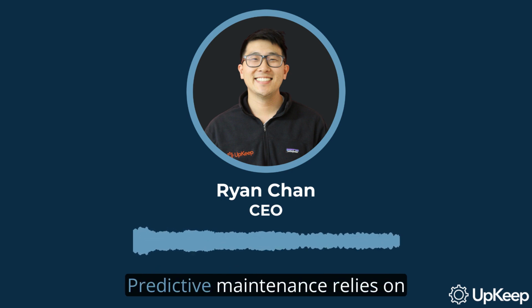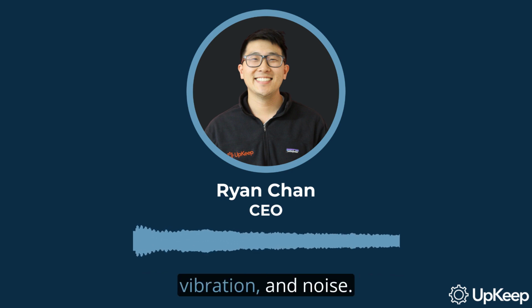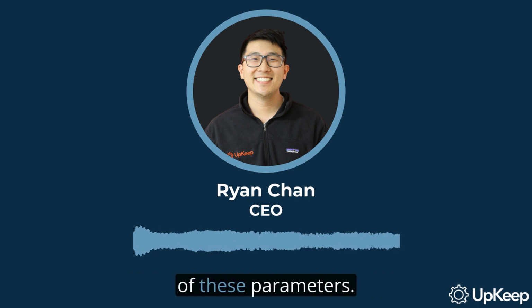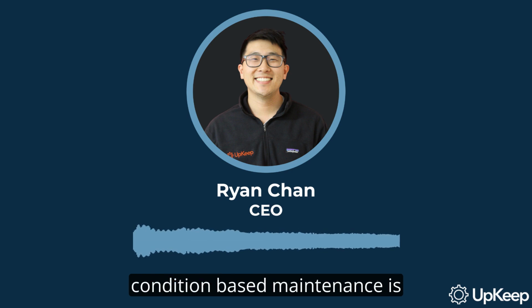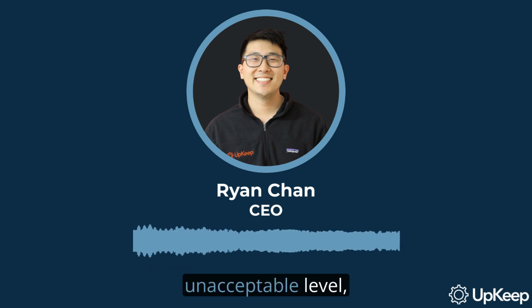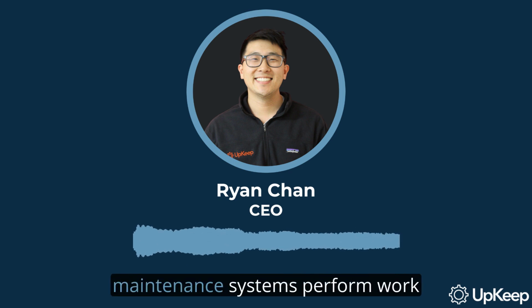Well, the primary difference lies in how maintenance is measured. Predictive maintenance relies on precise formulas and sensor measurements like temperature, vibration, and noise. Maintenance work is then performed based on the analysis of these parameters. This makes predictive maintenance a very exact form of maintenance because it predicts future maintenance events. On the other hand, condition-based maintenance is all about real-time sensor measurements. When a parameter hits an unacceptable level, maintenance workers are dispatched. This means that condition-based maintenance systems perform work only when it is needed.